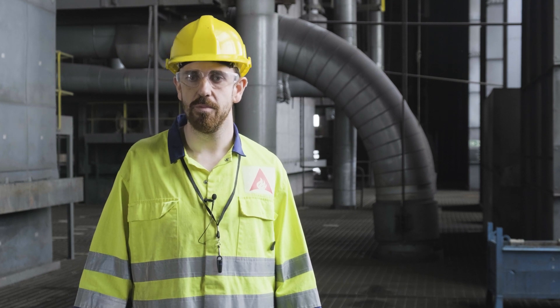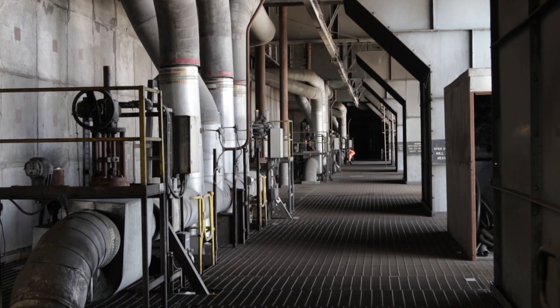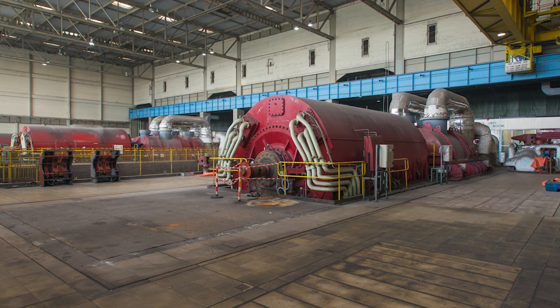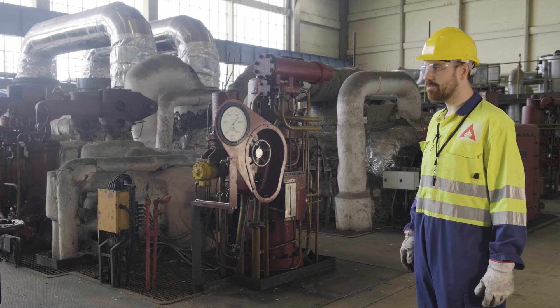It's here that the water picks up heat and is transferred into steam. The steam is then fed into the boiler drum where it's separated from the water and fed to what we call a superheater. In the superheater, we heat the steam to 543 degrees C before it's admitted to the turbine, ensuring that there's no moisture in the turbine by the time it finishes the power cycle.